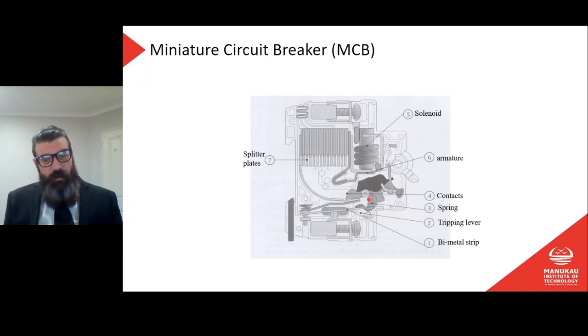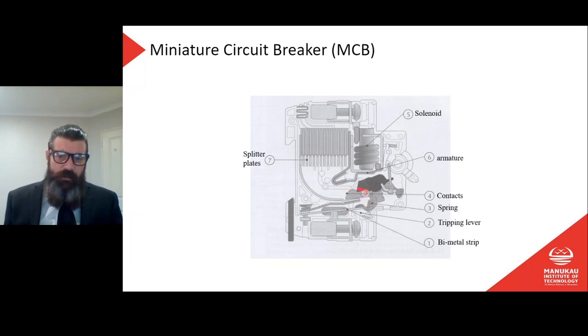Number 3 is the spring, which is going to pull the contacts. The contacts are being held in place, and when the tripping lever moves, no longer holding the contacts in place, the spring is going to pull that down, or is it pushing it up? The spring is pushing it up, I think, which is going to move the contacts and break our switch open, which is number 4, the contacts there. Number 5 is our solenoid. So now we're talking about the electromagnetic part. We can see there that coil around there. So the current is flowing through that coil. When it gets really high, we get a magnetic field there. And this part in the center, the little piston there, is going to be pushed down to the armature, which will again activate the tripping lever.